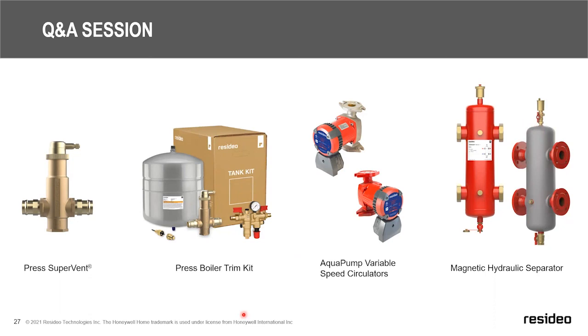Just got another question here about your new residential controls having no system pump connection. Why is that? Actually, our pump end switch does control the system pump on our HPZC boards. If you're having issues with that, just let us know. Give us a call and we can walk you through how best to wire that. Also, the domestic hot water circulator pump also does run off the first zone and can be used in application as well. And Mike, that was a great answer to that.